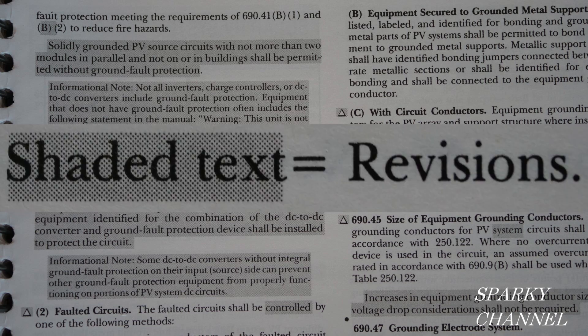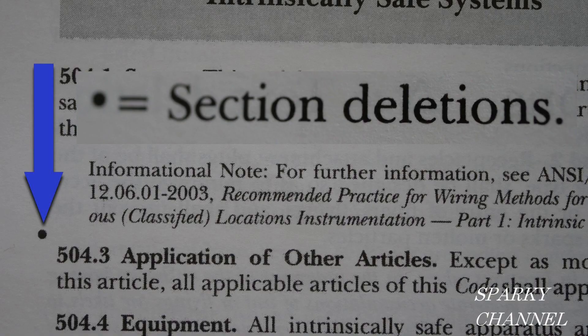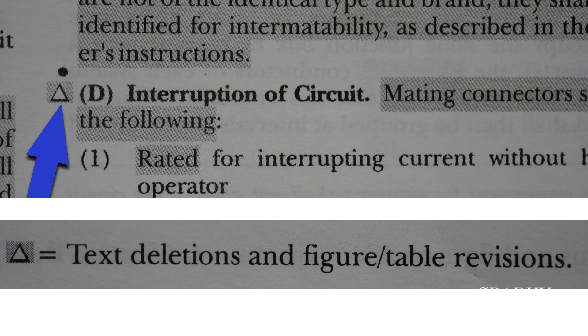Shaded text equals revisions. So for the 2020 NEC, if you see shaded text, something has been revised in that area. The period symbol you see right here before article 504.3 means section deletions — something right before article 504.3 has been deleted, and that little period alerts you to that situation. The delta symbol means text deletions and figure/table revisions. Note that this means text deletions, while the period means section deletions.